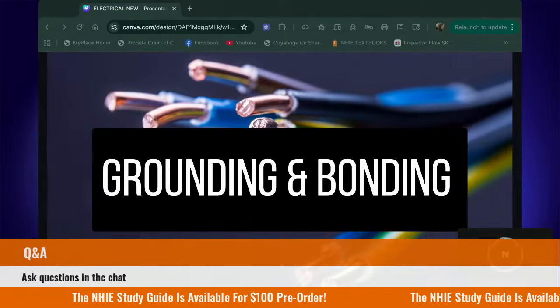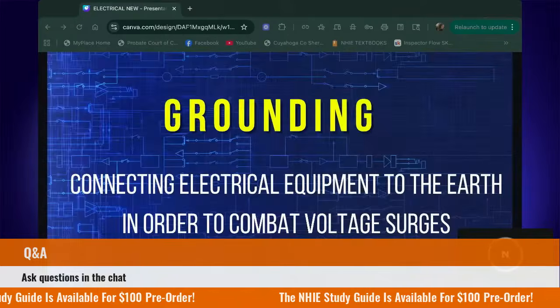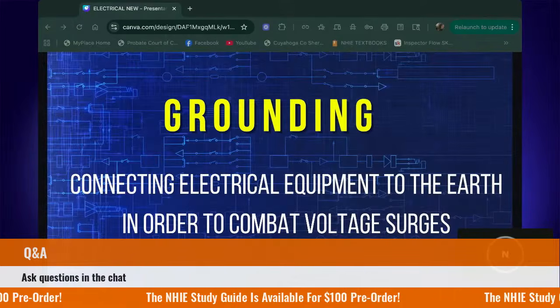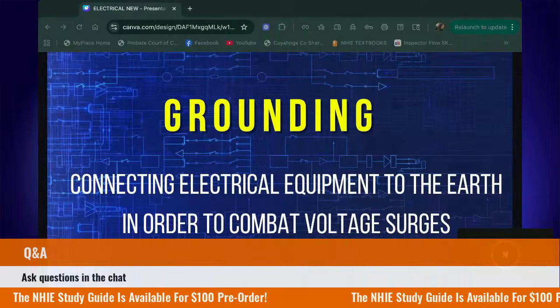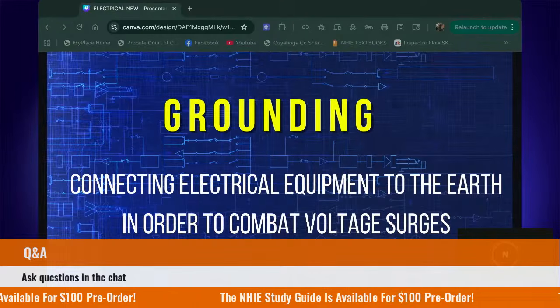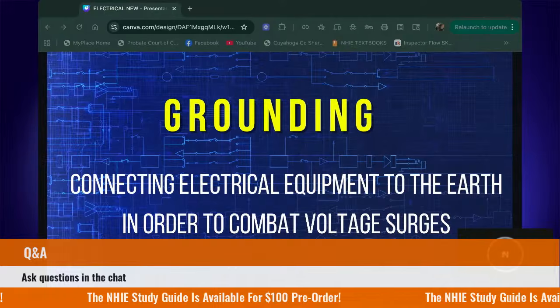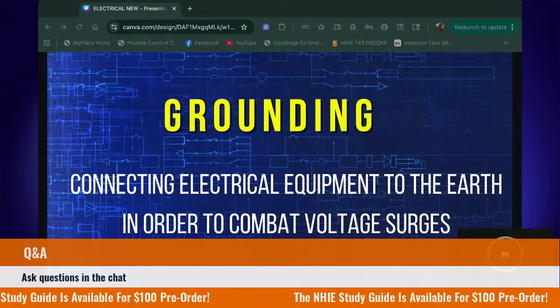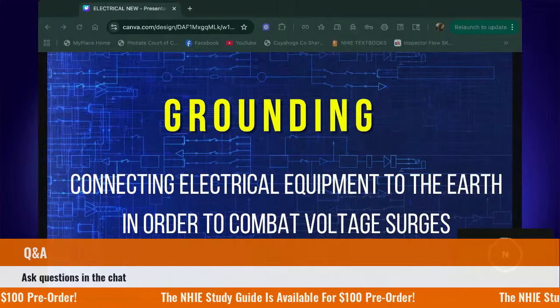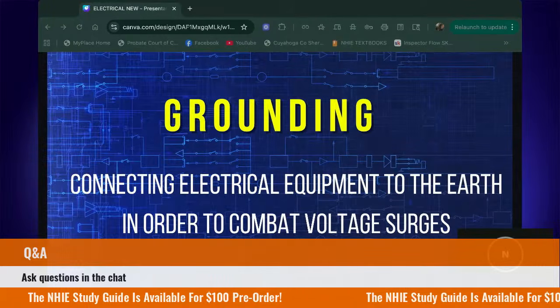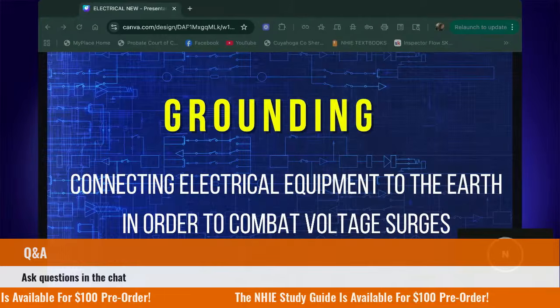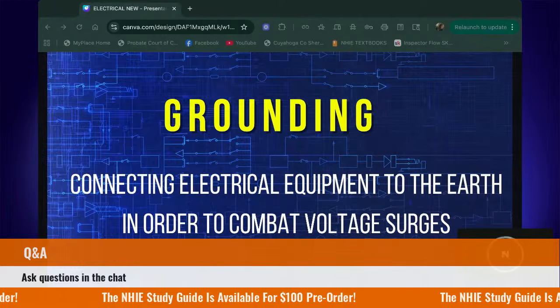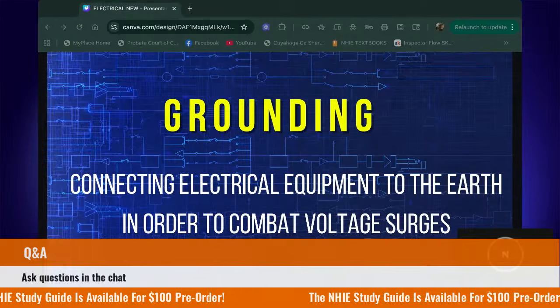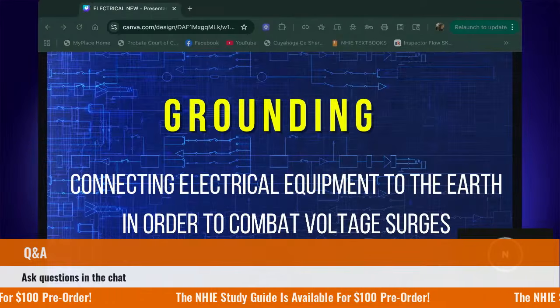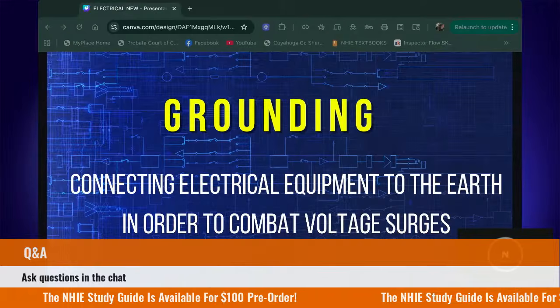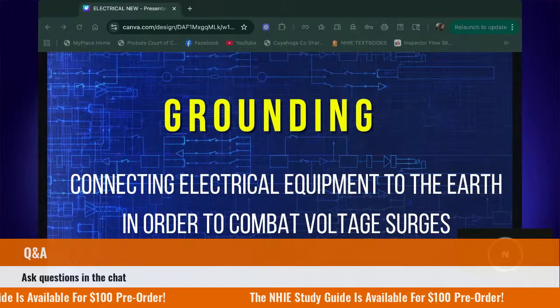Okay. All right. So let's talk specifically about grounding. Okay. So we ground the system to protect people and equipment. If you have again a hot wire that touches something metal or something that is conductive, the grounding system is what gives that electricity a shortcut to be able to leave before we have an issue. Okay, that path is what helps again the breaker to trip and kill the power before anybody gets shocked or before the wire has a chance to overheat.